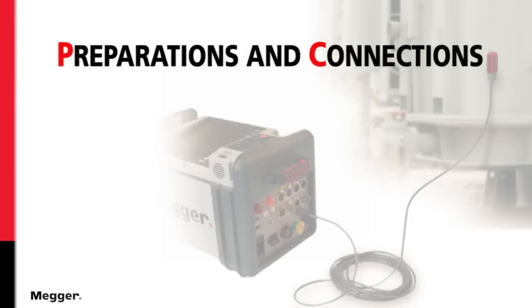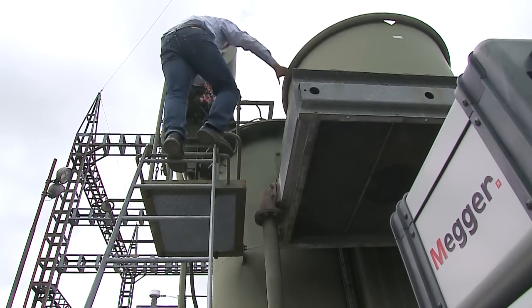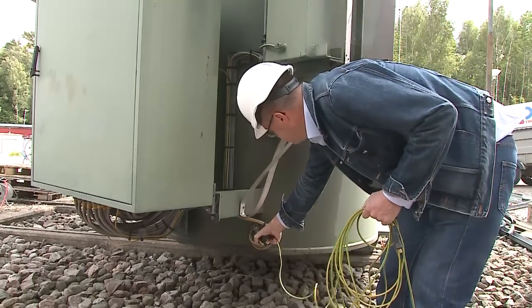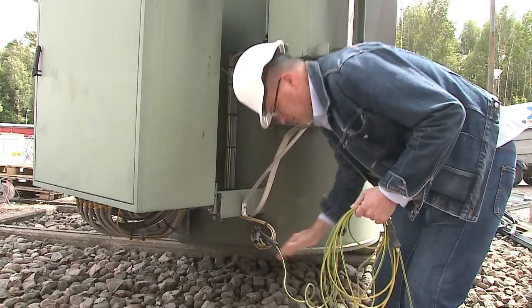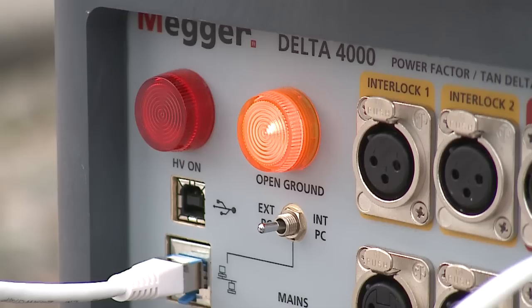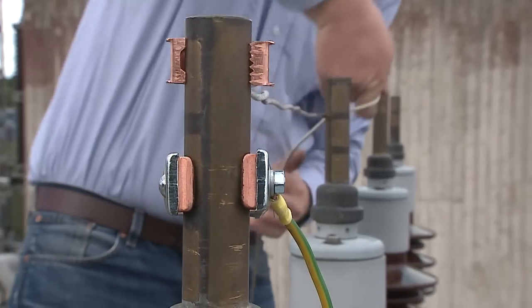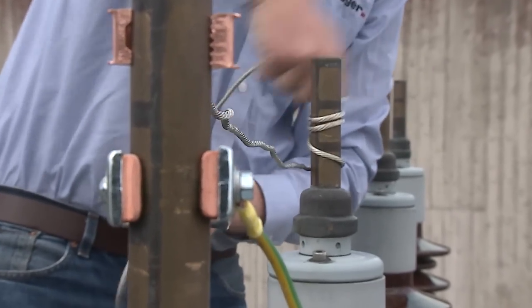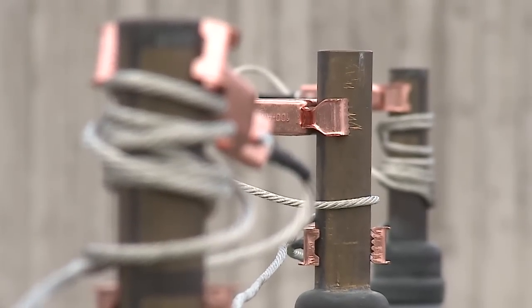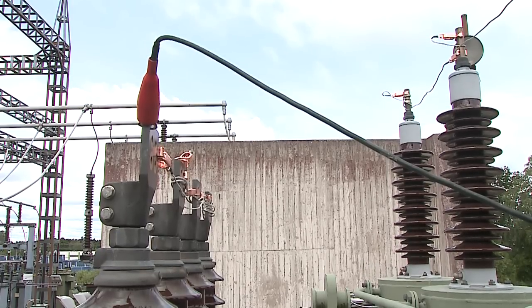Preparations and Connections: Remove all connections to the transformer bushings, including lightning arrestors and bus bar. Isolate neutral winding from ground connections. We prepare the Delta 4000 by connections to transformer ground. Short all phases for each winding together, ensuring shorting leads do not droop. Connect HV and low voltage red lead to windings. Transformer is now ready for testing.